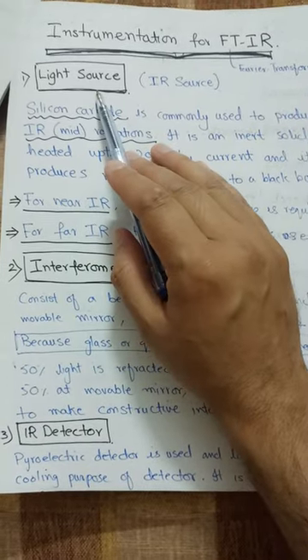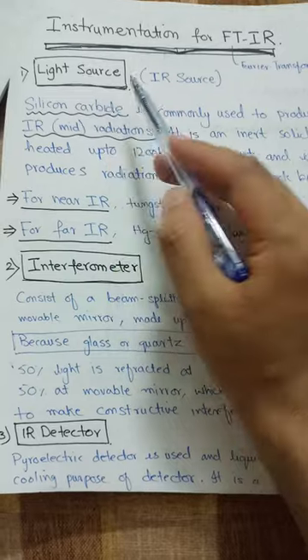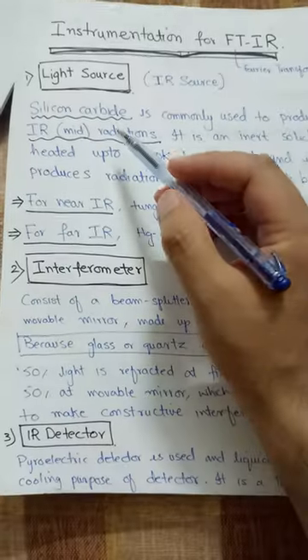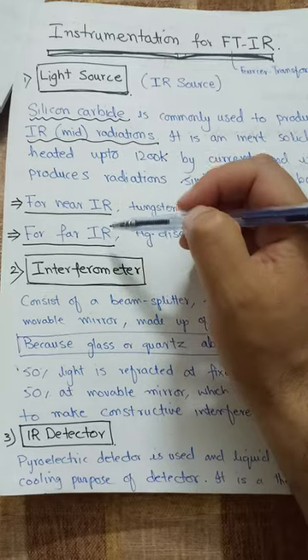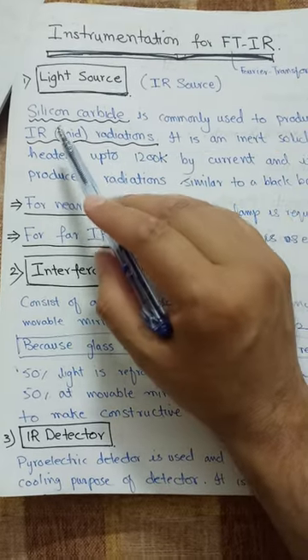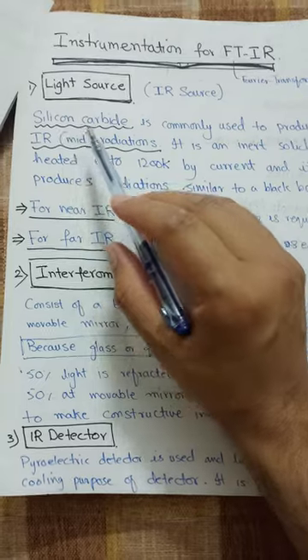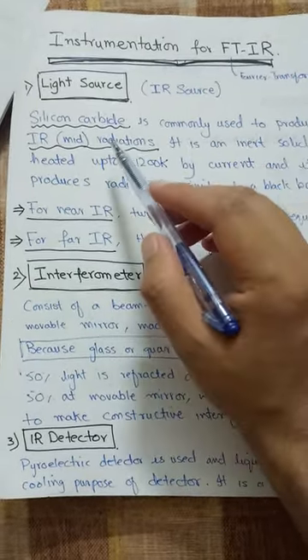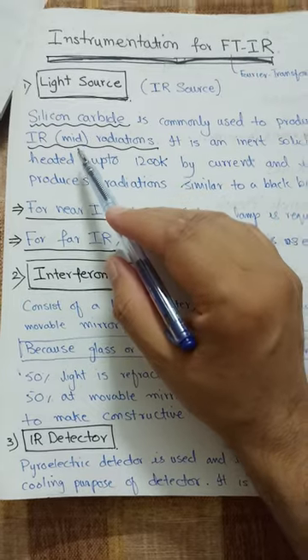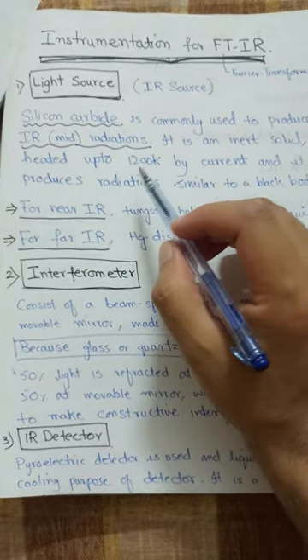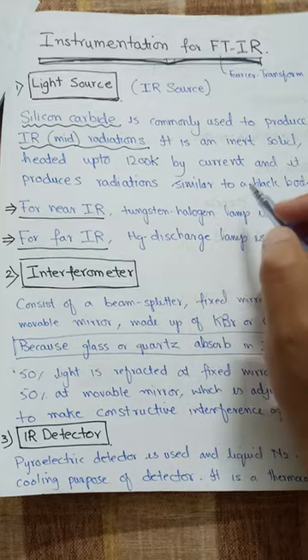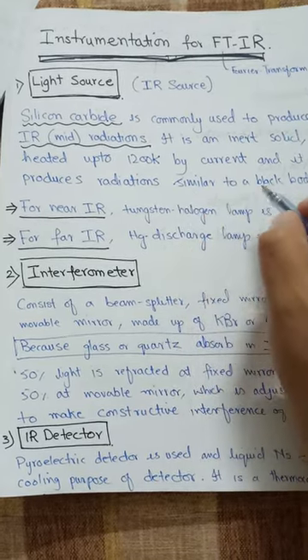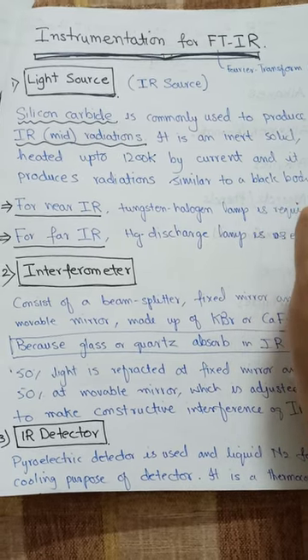First of all we will discuss the light source of the IR spectrophotometer. There are three types of light sources which produce three different types of radiations. For mid-infrared radiation we use silicon carbide, which is an inert solid. It is heated up to 1200 K by current and emits radiation similar to black body radiations.